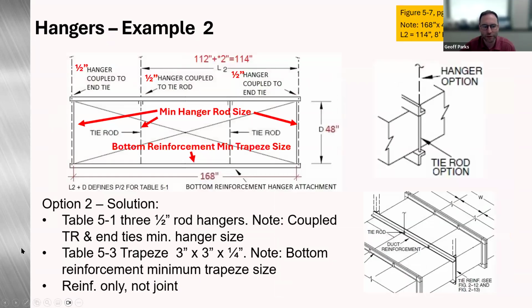So the option 2 solution was, 5-1. We have 3 1/2 inch rods. Note, this is going to be coupled to the tie rod. So both, your tie rod's also going to have to be sized to handle that load as well. And then table 5-3, the trapeze is again 3x3 by 1/4 inch. And this is a bottom reinforcement, minimum trapeze size. So we have options to add a third hanger rod, either at the midpoint or tie into a tie rod to kind of minimize that trapeze size and your rod size as well.